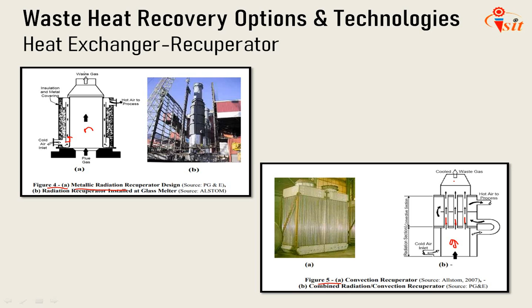Recuperators are constructed of either metallic or ceramic materials. While metallic recuperators are used in applications with temperatures below 1093 degrees Celsius, heat recovery at higher temperature is best suited to ceramic tube recuperators. These can operate with hot side temperature as high as 1538 degrees Celsius and cold side temperature of around 982 degrees Celsius.